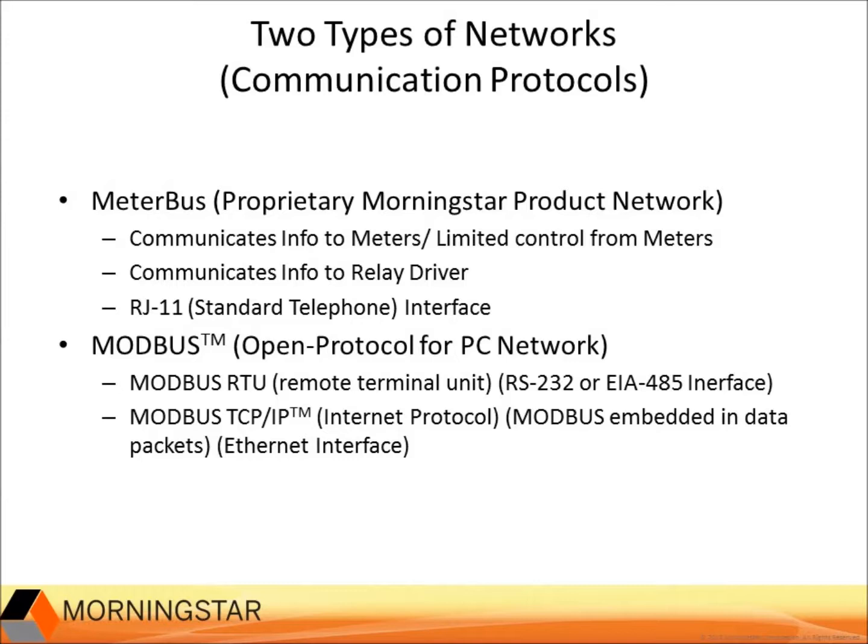TCP/IP is for networks that use IP addresses for local area networks or internet communications. This uses an Ethernet interface. It is important to note that a Modbus network is completely separate from the Meterbus network. It will not provide a connection to the Meterbus, so if you need a connection to multiple devices at a site, it needs to be a Modbus connection. The Meterbus network can only talk to the meters and relay driver.